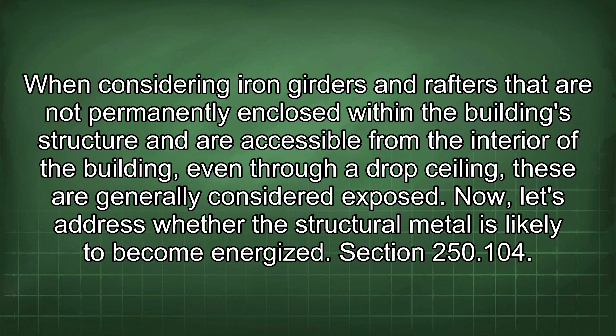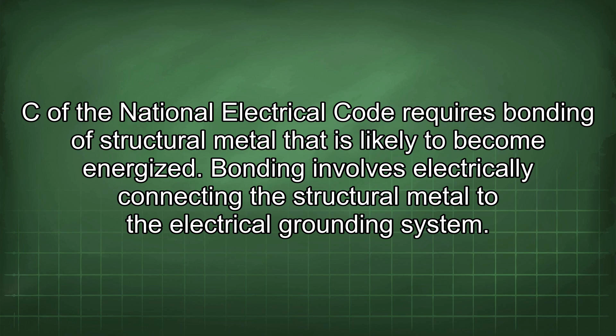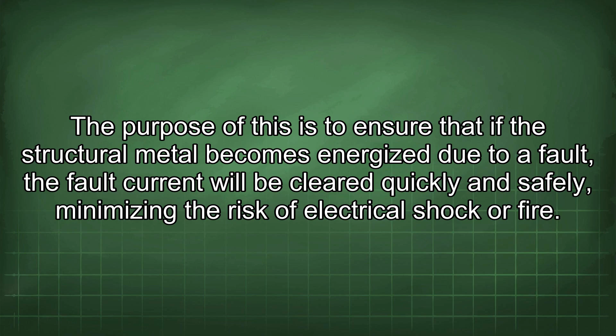Now let's address whether the structural metal is likely to become energized. Section 250.104(C) of the National Electrical Code requires bonding of structural metal that is likely to become energized. Bonding involves electrically connecting the structural metal to the electrical grounding system, to ensure that if it becomes energized due to a fault, the fault current will be cleared quickly and safely, minimizing the risk of electrical shock or fire.